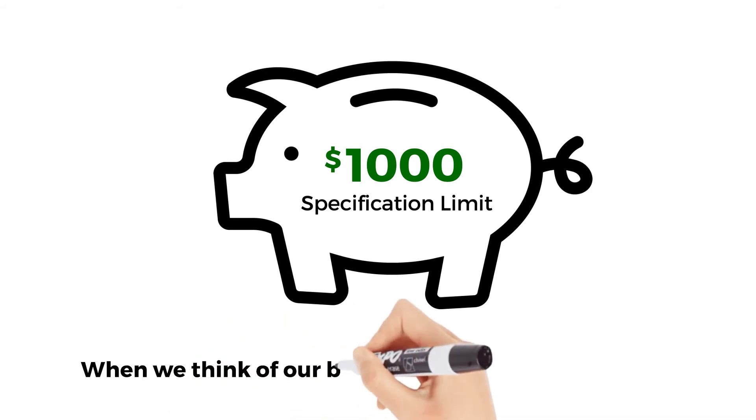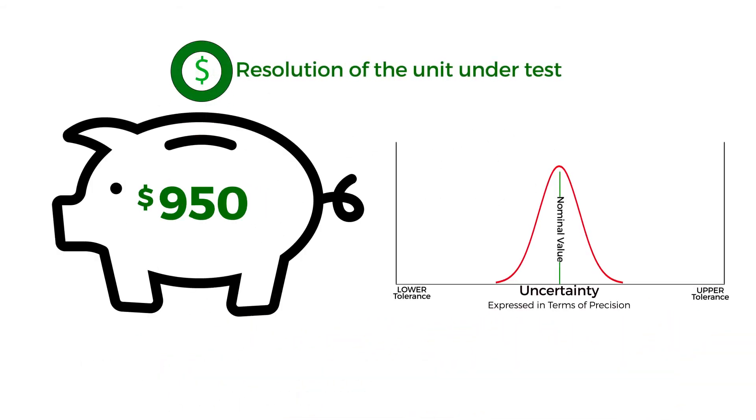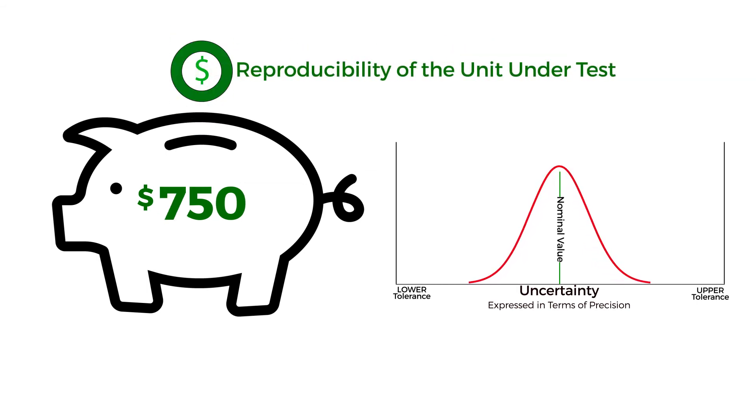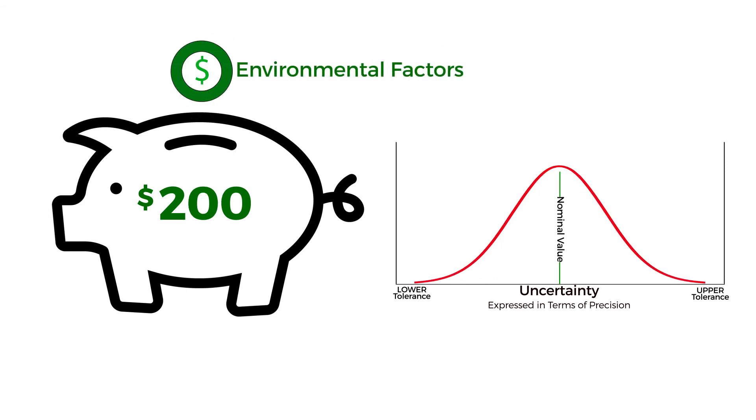When we think of our budget in terms of uncertainty, the expenses are resolution of the unit under test, repeatability of the unit under test, reproducibility of the unit under test, reference standard uncertainty, reference standard stability, environmental factors.